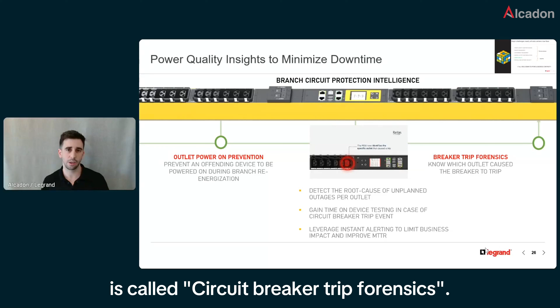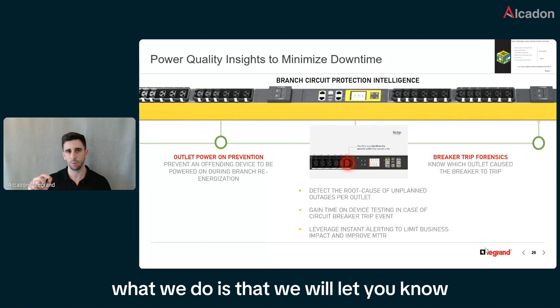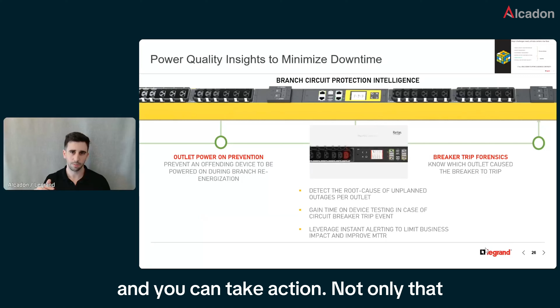So we included something called circuit breaker trip forensics. When a trip happens, we let you know which outlet had the problem, so you can automatically pinpoint the server that needs servicing and take action. We also automatically take screenshots of all the metrics for that outlet so you can analyze the root cause.